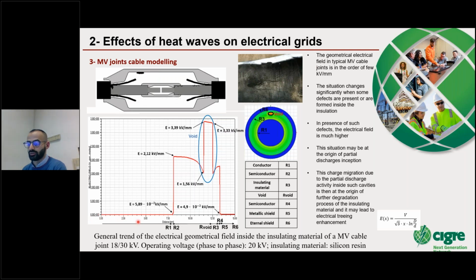We can see that along the thickness of the insulating material, the electric field is normally around 2 kV/mm, but it increases when we are in presence of a void, for example. This value is critical because it could be greater than the electric strength of the air, and can be at the origin of partial discharge and also of the final failure.